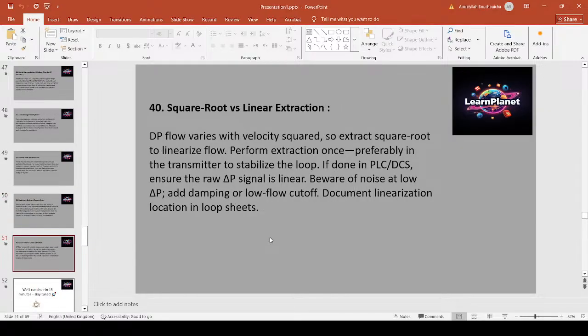DP flow varies with velocity squared, so extract the square root to linearize flow performance. Extract once, preferably in the transmitter, to stabilize the loop. If done in the PLC or DCS, ensure the raw delta P signal is linear. Beware of noise at low delta P. Add damping or low flow cutoff. Document the linearization location in loop sheets.